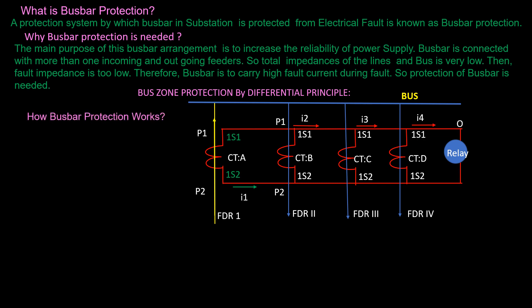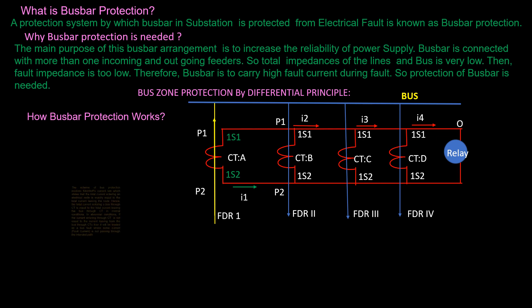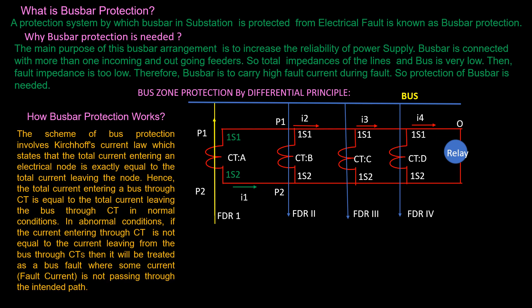How does busbar protection work? The scheme of bus protection involves Kirchhoff's current law, which states that the total current entering an electrical node is exactly equal to the total current leaving the node. Hence the total current entering a bus through CTs is equal to the total current leaving the bus through CTs in normal conditions. In abnormal, that is faulty conditions, if the current entering through CTs is not equal to the current leaving the bus through CTs, then it will be treated as a bus fault.